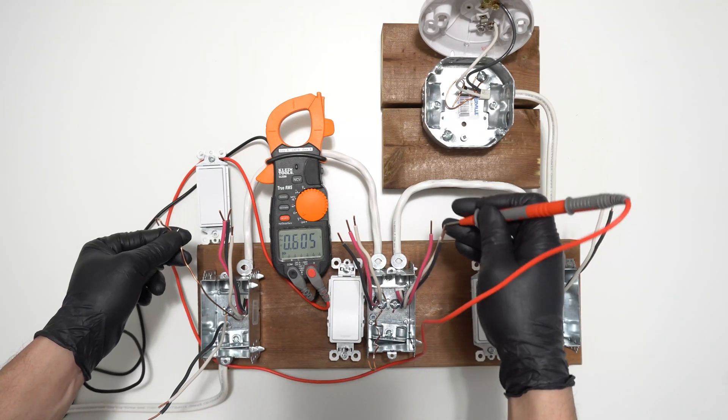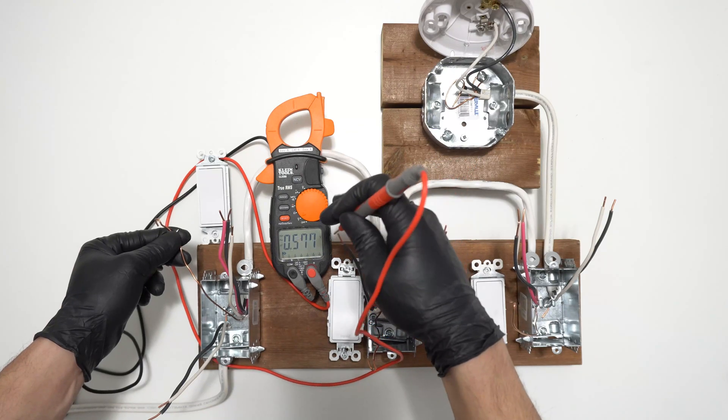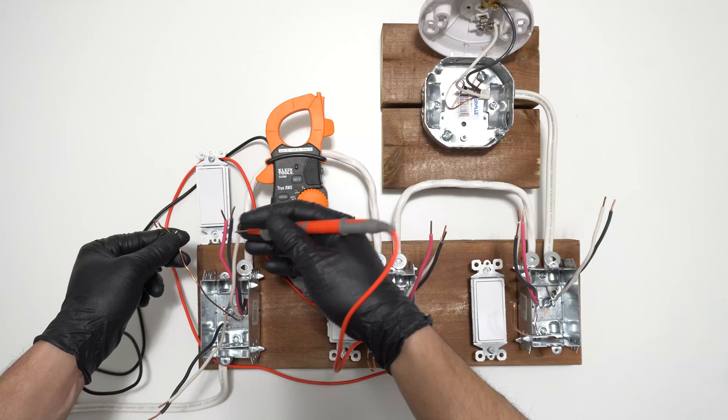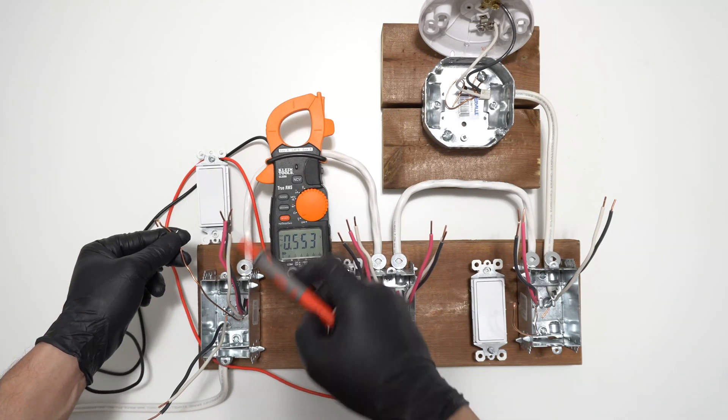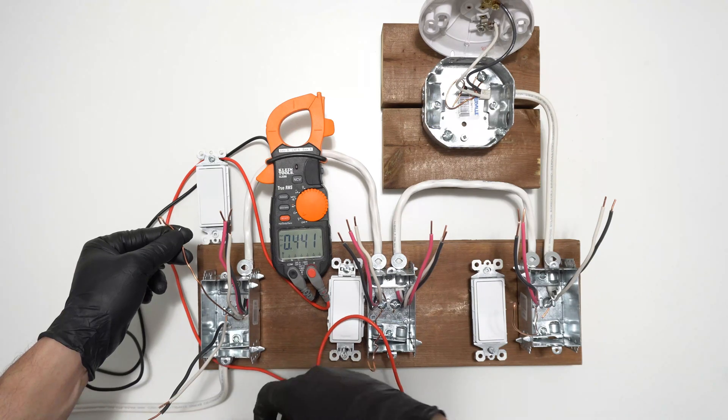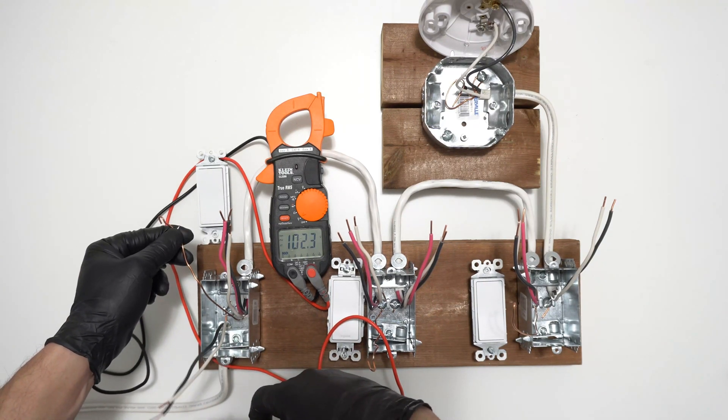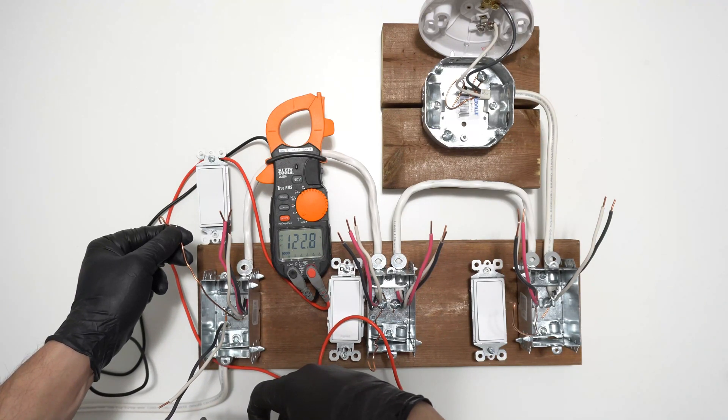And if we have a potential jump, that means the circuit is not turned off. Don't worry about these low voltage values. Here we have a potential difference close to 120. That means the breaker is still not turned off.